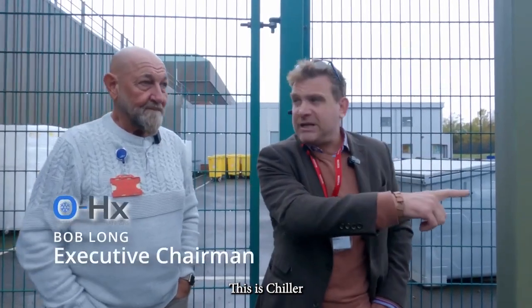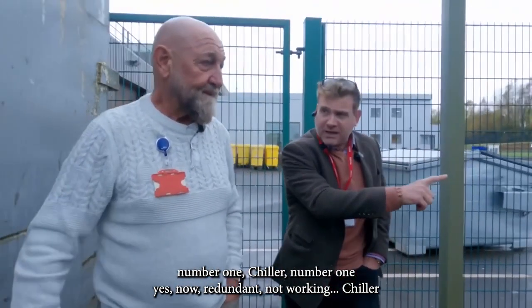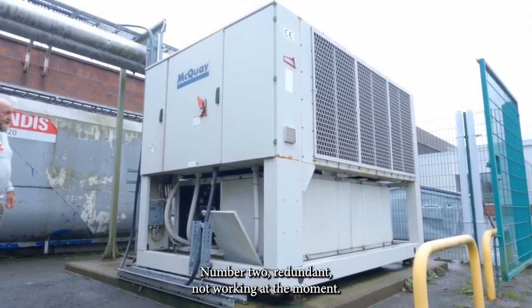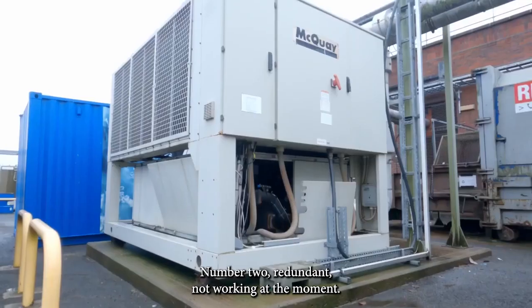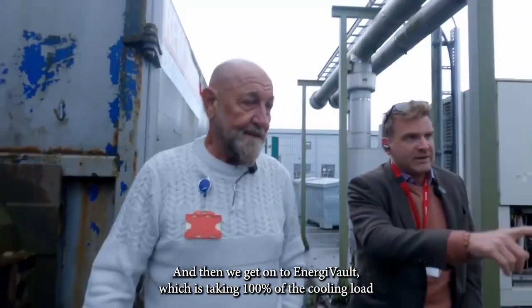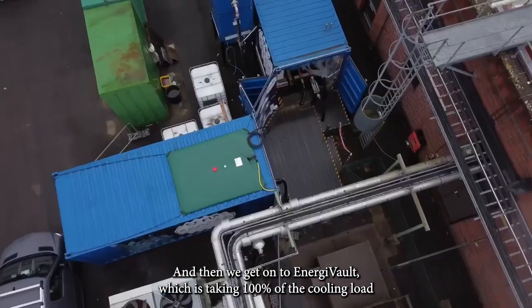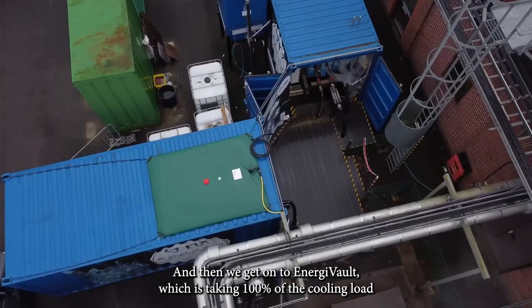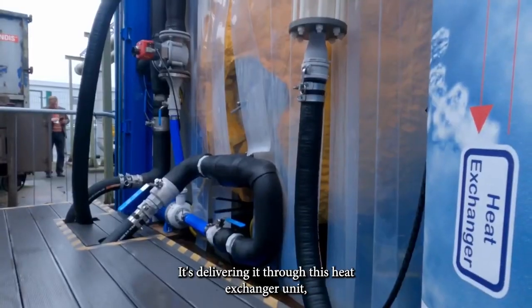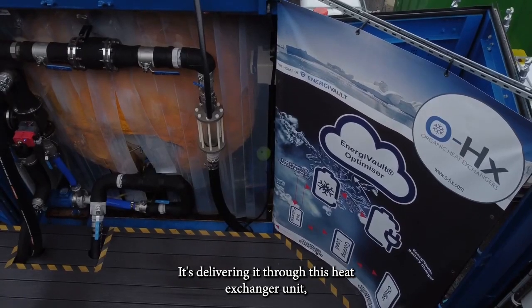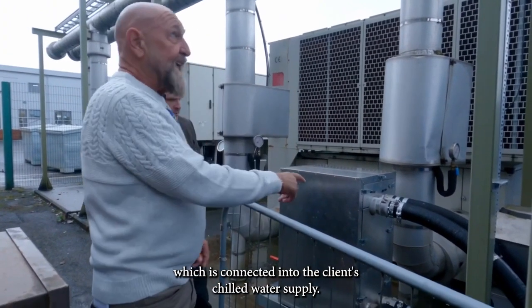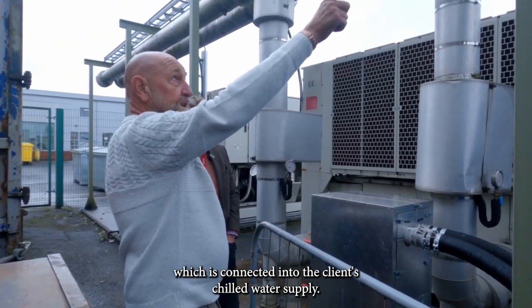Chiller number 1, now redundant, not working. Chiller number 2, redundant, not working at the moment. And then we get on to EnergiVault, which is taking 100% of the cooling load at the moment. That's correct, yes. It's delivering it through this heat exchange unit, which is connected into the client's chilled water supply.